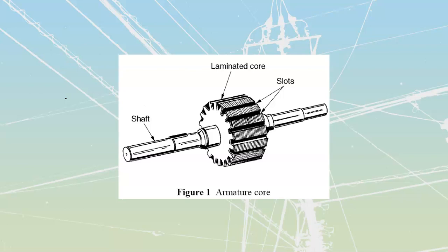My DC generators and DC motors are going to be built in the same way except for the enclosures. For generators, they're usually not placed in incredibly dirty or dusty locations, so they're typically open for access to components, connections, maintenance, and airflow for cooling. In contrast, DC motors are usually placed into dirty service — inside mills and mines — which means we need sealed units so the crud of the working world doesn't get inside. Other than that major difference, the construction is the same. I can hook a generator up to electricity and it becomes a motor, or rotate a motor shaft and it becomes a generator.